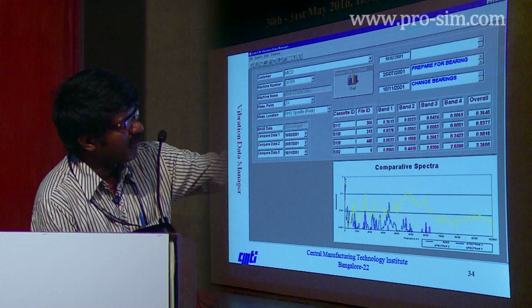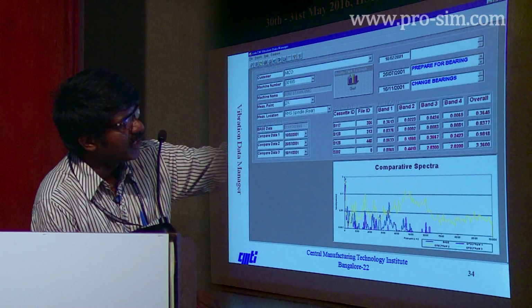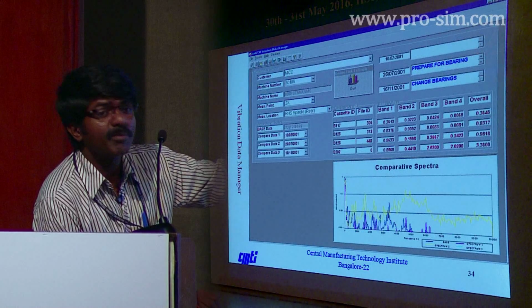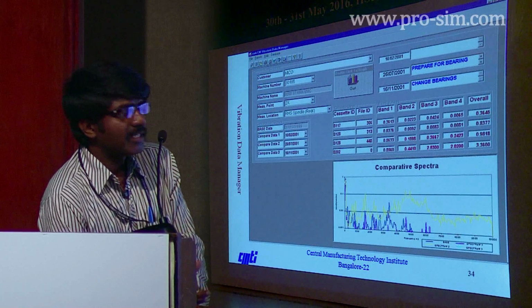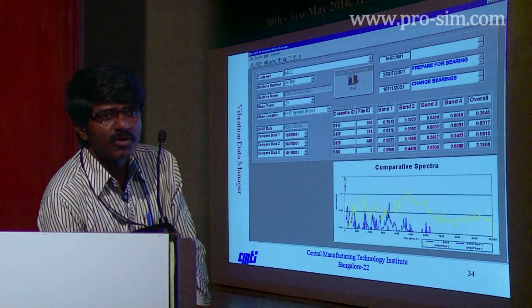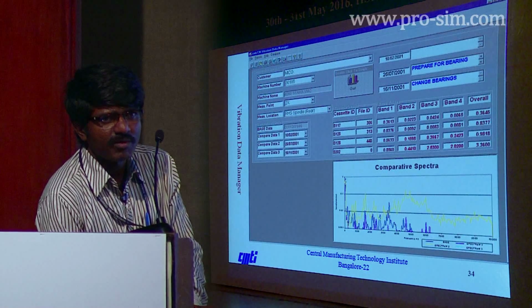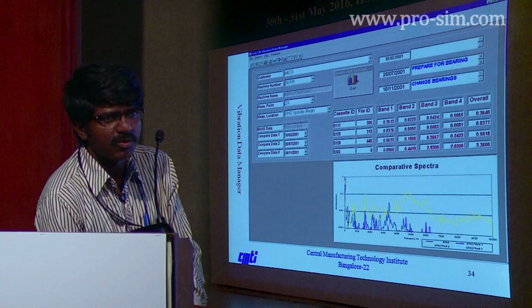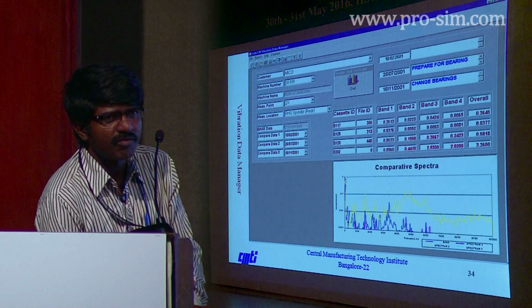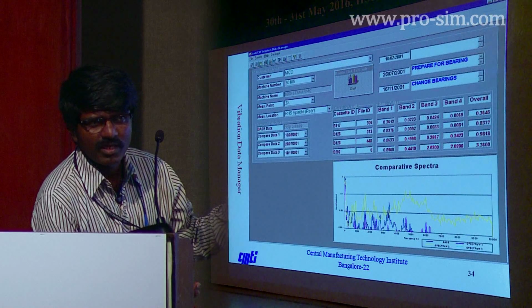And also, for example, if you see here, in condition monitoring we will give you an advance warning like prepare for bearing change, because it takes some time for maintenance people to procure the bearings. So we have to give some lead time, at least 2 to 3 months. The moment they finish all these activities, they can go for the bearing replacement.